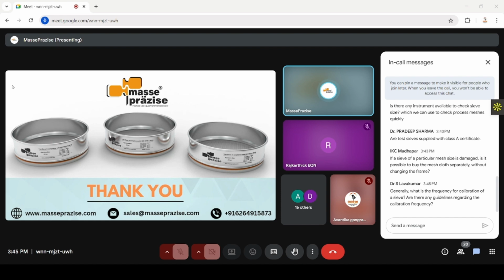Is there any instrument available to check sieve size which we can use to check the mesh quickly? Yes, there are instruments that can be used for checking the test sieve. Especially for the large size test sieves, there are linear mesh counters, there are pen microscopes, and calibrators are also available, like a magnifying glass with scales. There are also go and no-go pins for sizes above 100 micron. Go/no-go pins are widely available for every size, and pen microscopes are available for fine sizes with scales. So this type of instrument can be used for daily checking of the test sieves.